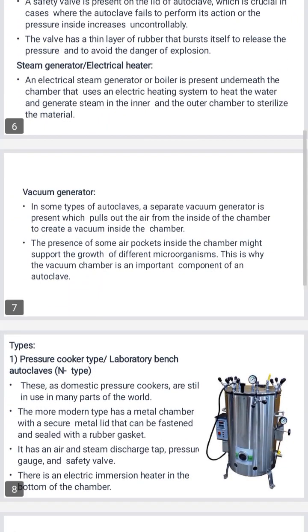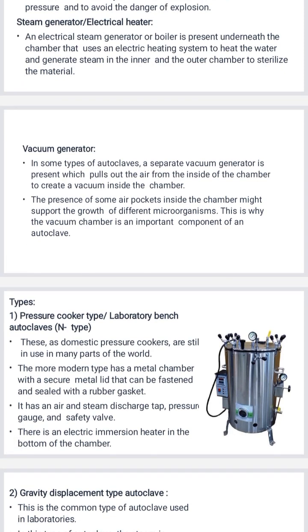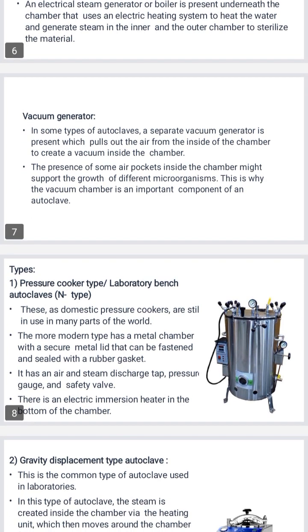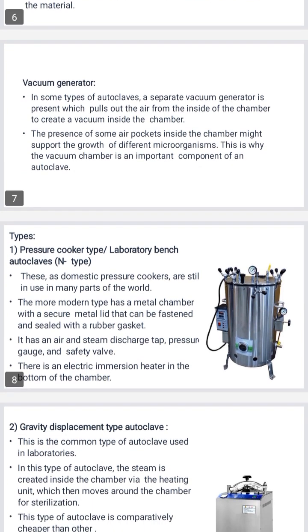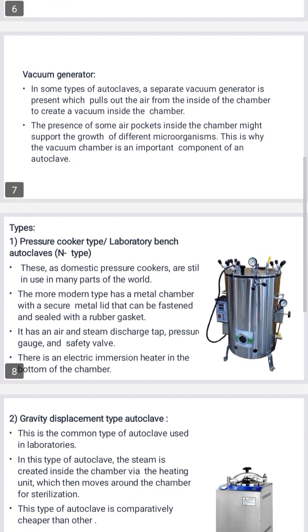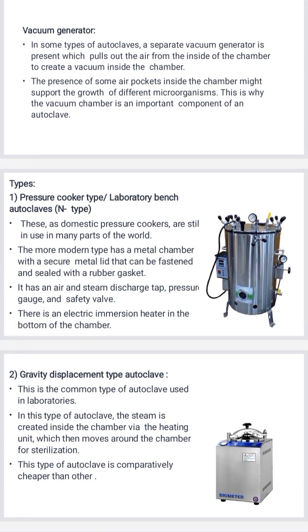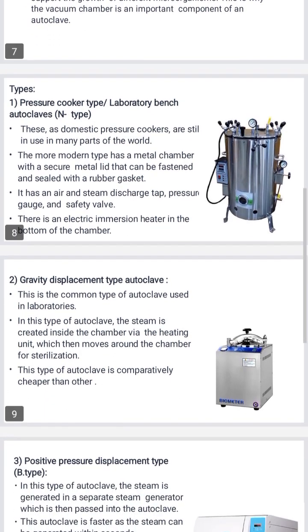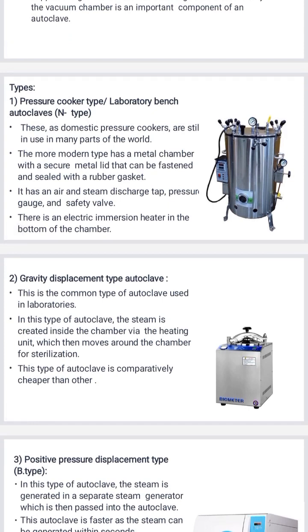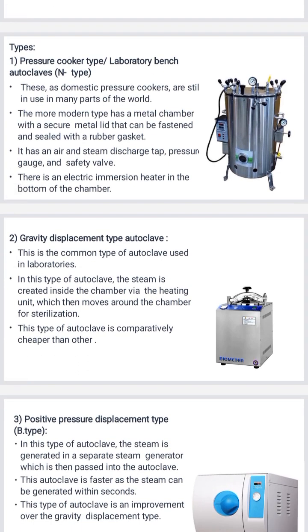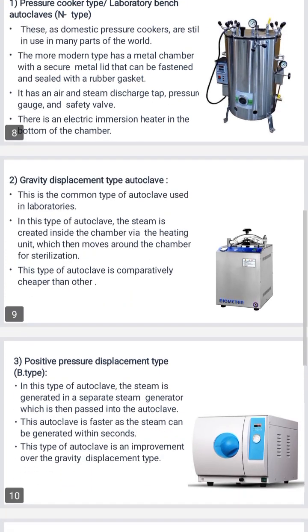Now the types of autoclave. The pressure cooker type, laboratory bench autoclaves. This is like the domestic pressure cooker, still in use in many parts of the world. The more modern type has a metal chamber with a secure metal lid that can be fastened and sealed with a rubber gasket. It has an air and steam discharge tap, pressure gauge and safety valve. There is an electric immersion heater in the bottom of the chamber.